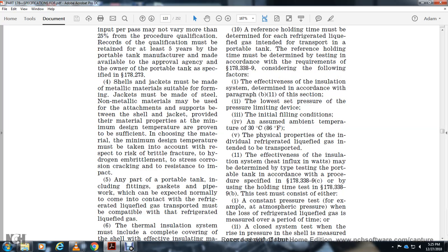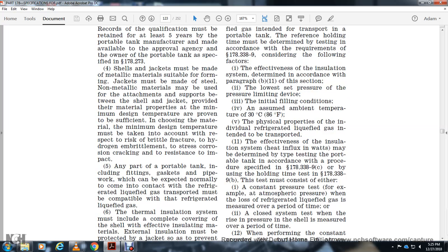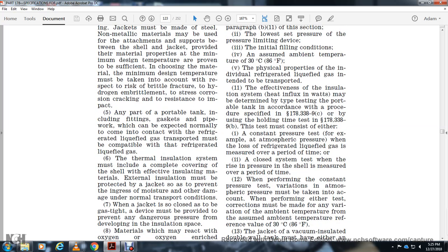The test must consist either of a constant pressure test, for example at atmospheric pressure, where the loss of the refrigerated liquefied gas is measured over a period of time, or a closed system test where the rise in pressure of the shell is measured over a period of time. When performing constant pressure tests, variation in atmospheric pressure must be taken into account.